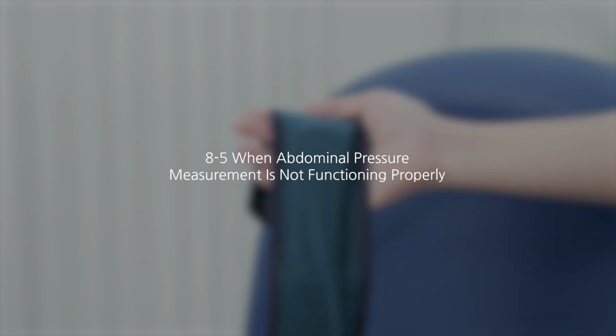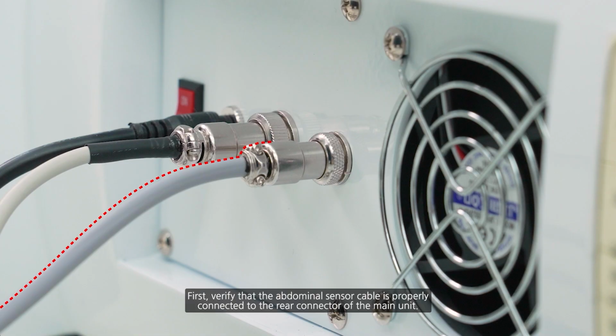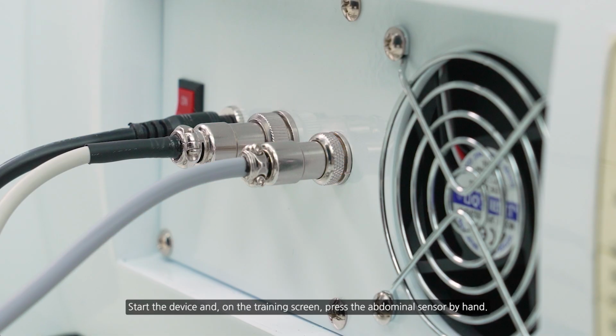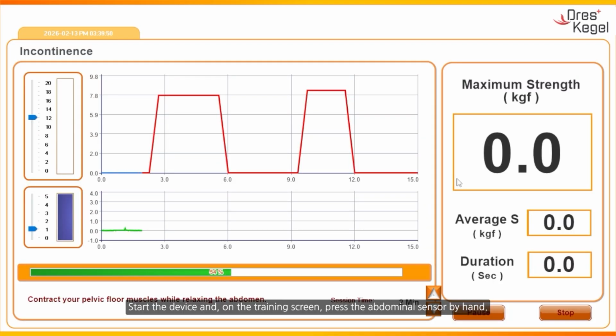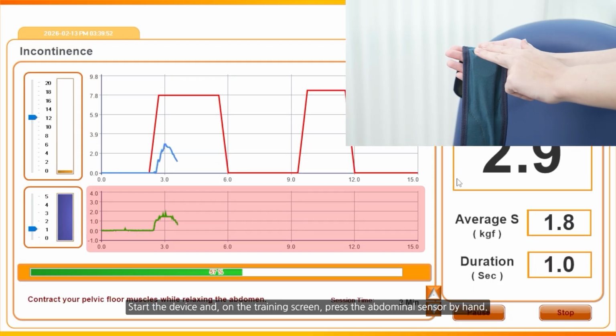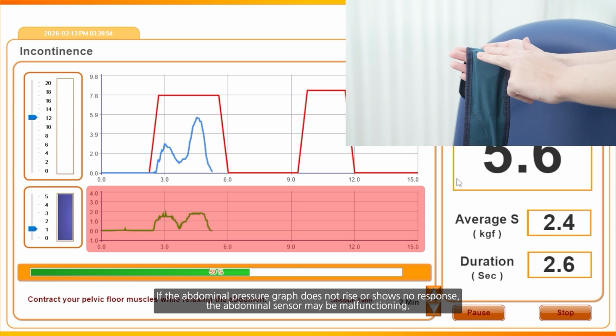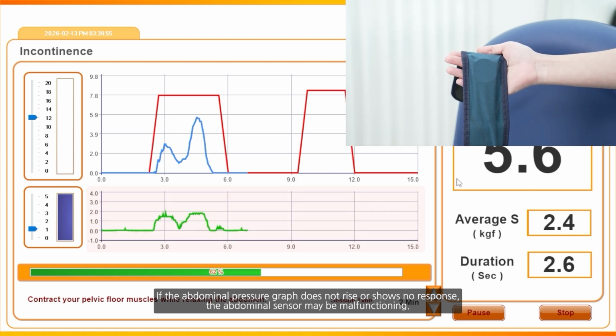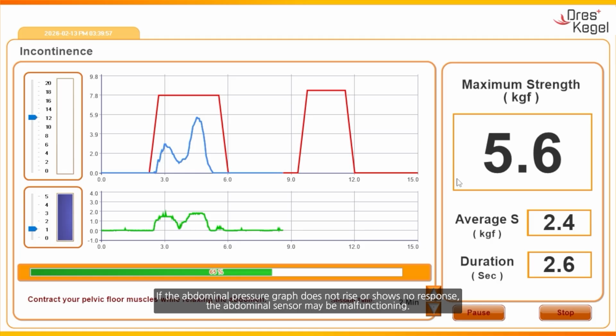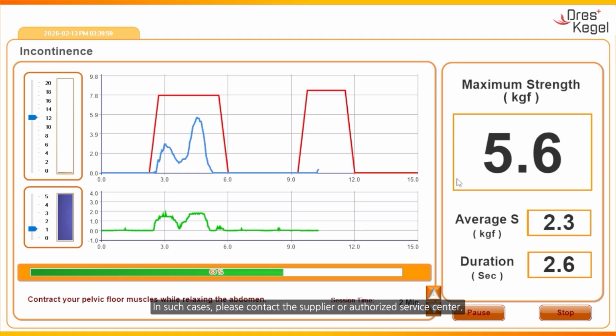Number 8-5. When abdominal pressure measurement is not functioning properly. First, verify that the abdominal sensor cable is properly connected to the rear connector of the main unit. Start the device and, on the training screen, press the abdominal sensor by hand. If the abdominal pressure graph does not rise or shows no response, the abdominal sensor may be malfunctioning. In such cases, please contact the supplier or authorized service center.